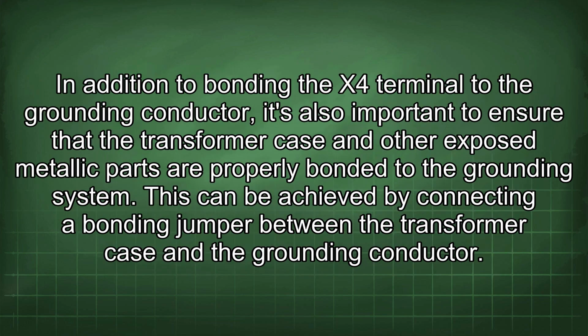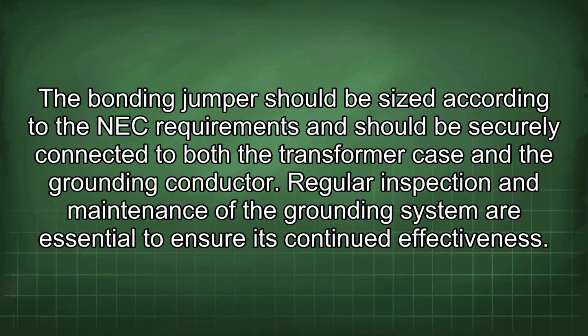In addition to bonding the X4 terminal to the grounding conductor, it's also important to ensure that the transformer case and other exposed metallic parts are properly bonded to the grounding system. This can be achieved by connecting a bonding jumper between the transformer case and the grounding conductor. The bonding jumper should be sized according to the NEC requirements and should be securely connected to both the transformer case and the grounding conductor. Regular inspection and maintenance of the grounding system are essential to ensure its continued effectiveness.